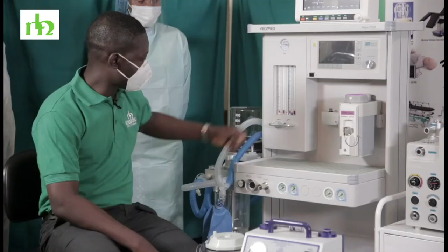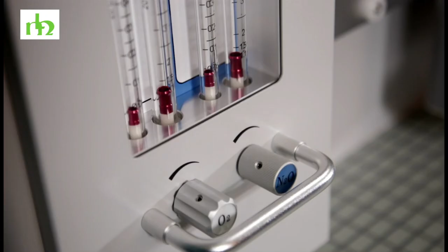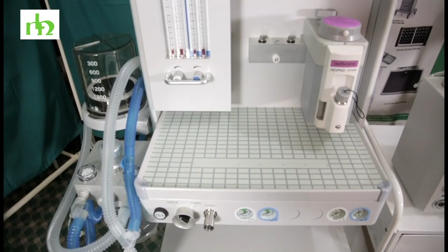So for this one, we have the flow meter for oxygen and also N2O, nitrous oxide. Of course, this machine has the function of delivering guaranteed oxygen when you try to administer nitrous oxide to the patient. It also has a very wide working surface where the anesthetist can easily work. There's a work area. And also, it has the ACGO function, that's auxiliary common gas outlet function. And here is the outlet when you turn on the switch here.